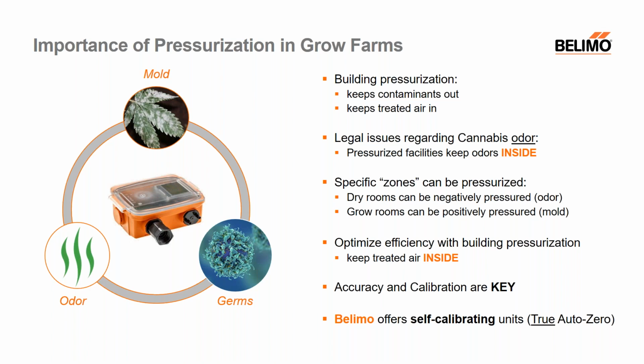By positively pressurizing a grow environment, you're also able to keep contaminants out of the facility, which will reduce potential mold growth and plant disease. Again, with a positively pressurized room, when doors and windows are open, the clean and treated air moves outward, thus eliminating any contaminated air from entering your grow facility. With proper pressure management within any facility, you can also drive expenses down and increase potential profitability. Tons of electricity and time is spent on conditioning the air within a building or grow facility. So by using Belimo's pressure sensors, you can ensure that this conditioned air stays within the walls of the grow farm or facility itself.